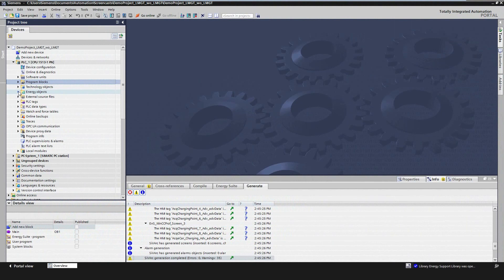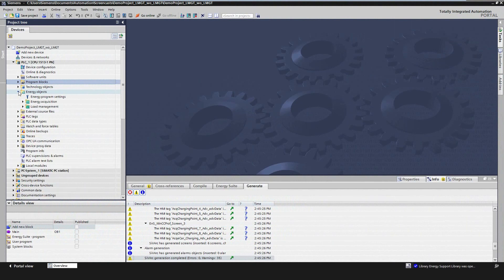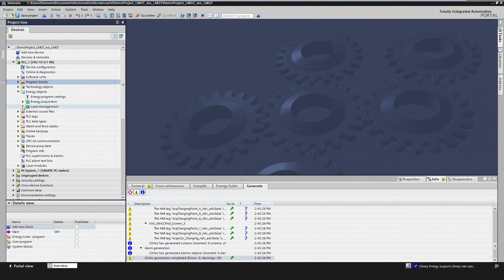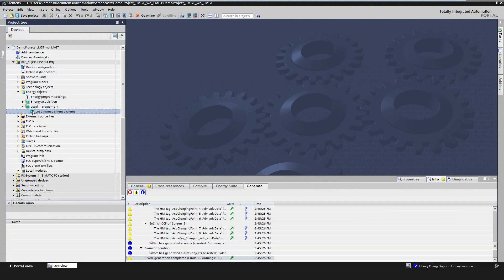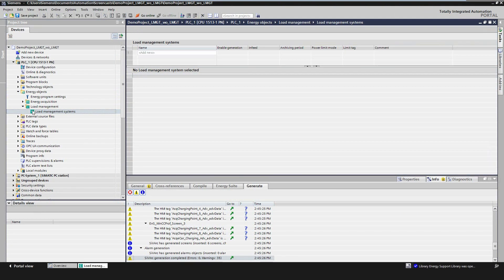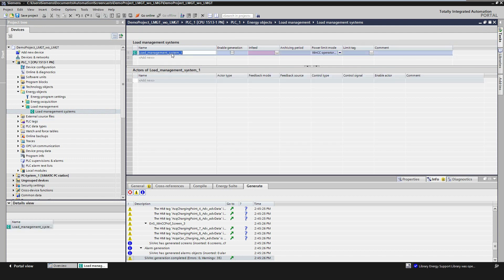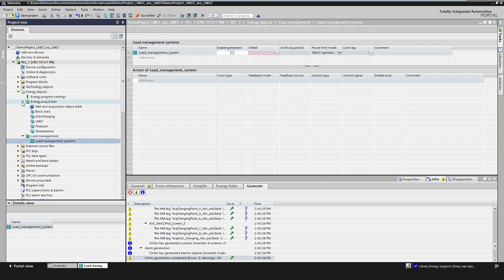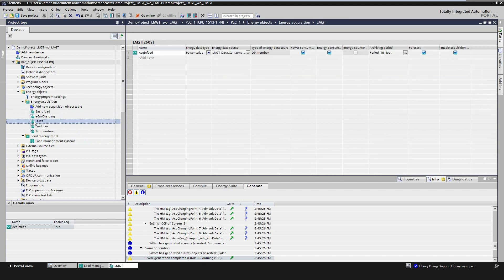Now let's switch over to the engineering of the integrated load management. The mechanism for using the load management software is the same as already known for the acquisition program. That means the user only has to configure the system. The PLC code will be generated automatically afterwards. One requirement for using the load management is that the infeed has been created as an acquisition object. For this object, the property forecast must be selected to automatically create a forecast for the actual period based on its consumption.